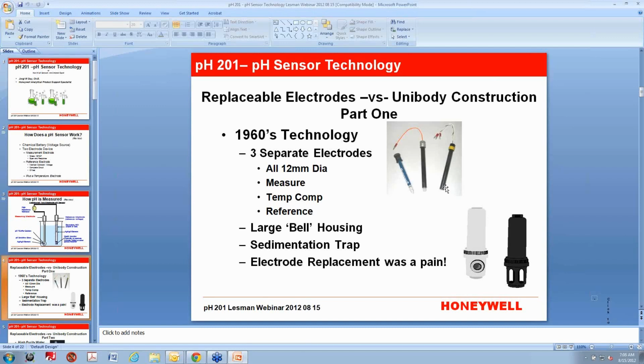So they're the same components that you would have in what we would call a unibody construction, which is what most people are familiar with, but they're separate electrodes. So if one dies, you can just take it out and replace it. It comes in a large bell housing. Housings are at the bottom right-hand side, and these may or may not contain a preamplifier in the top. It's nice because you can replace a single electrode, like the measuring electrode if that's what's failing in your process, or the reference electrode if that's what's having a problem.